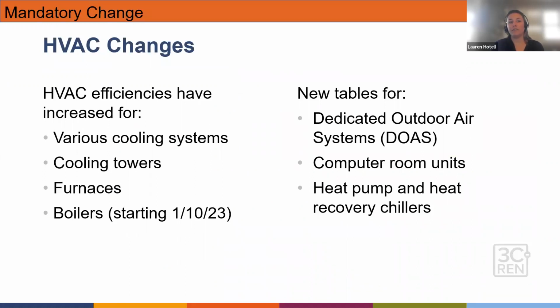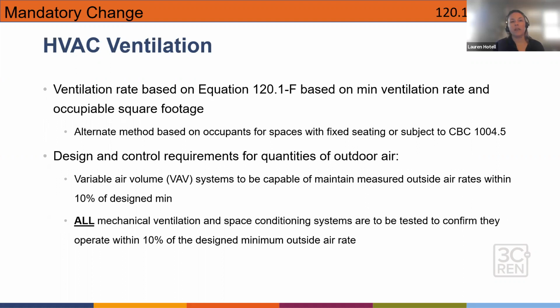Some of the HVAC changes we're seeing for 2022: there have been increased efficiencies for various cooling systems, cooling towers, furnaces, and boilers, starting at a later date. And there are some new tables for dedicated outdoor air systems, computer room units, and heat pump and heat recovery chillers. Ventilation rates are based on the minimum ventilation rate and occupiable square footage, with an alternate method based on occupants for spaces with fixed seating. Design and control requirements for quantities of outdoor air have also changed. All mechanical ventilation and space conditioning systems need to be tested to confirm they operate within 10% of the minimum outside air rate, and variable air volume systems need to be capable of maintaining measured outside air rates within 10% of the design minimum.